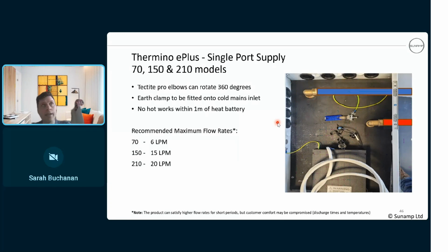With that in mind, if you do have a vertical rise, what we're finding is you're getting this thermal siphoning happening. So your heat losses may be increased due to a vertical rise coming straight off the battery. What we'd be recommending, it's not a must, is having a small U-bend to stop that vertical rise. That down rise is going to stop any heat escaping, because heat wants to go up, doesn't it? And then obviously you can go up if you want to.